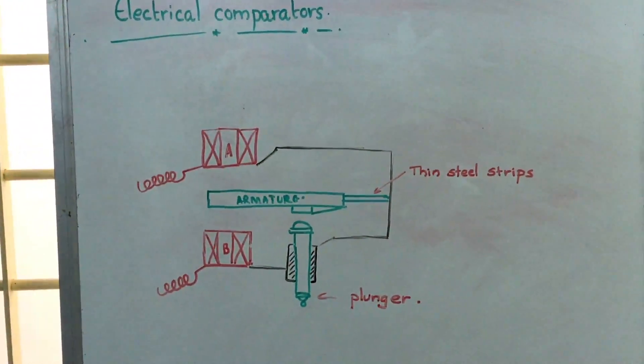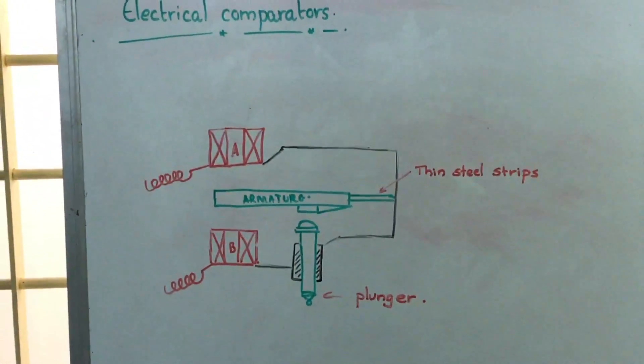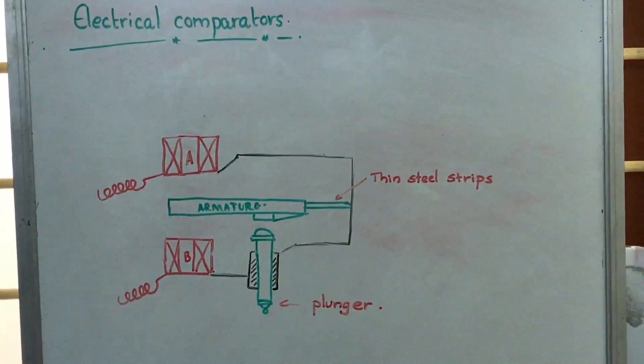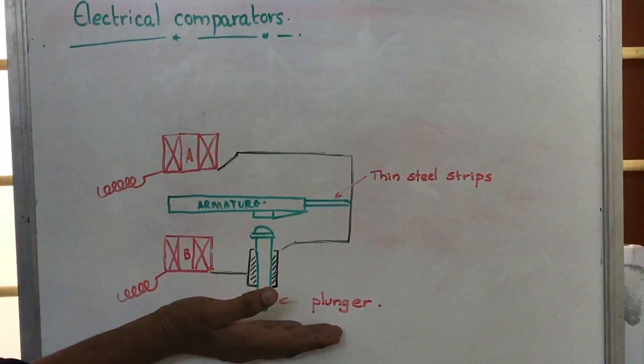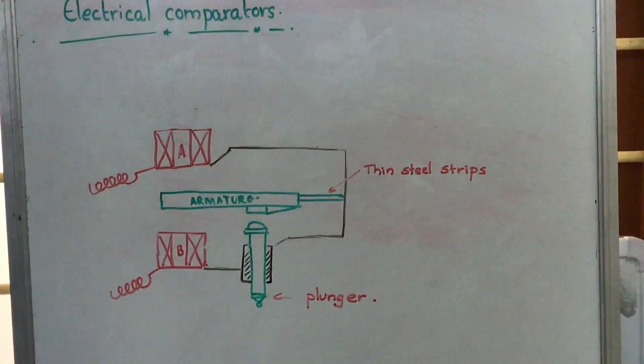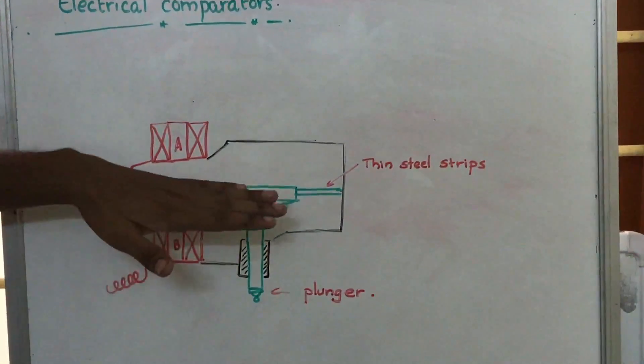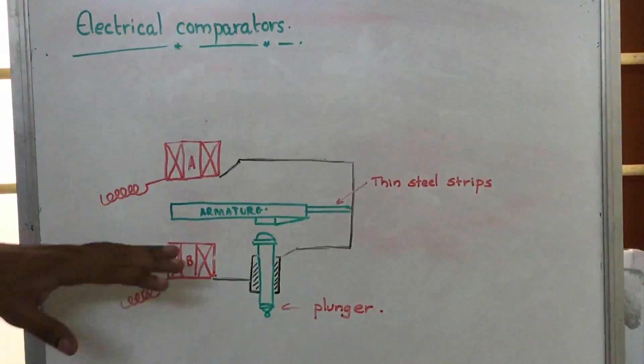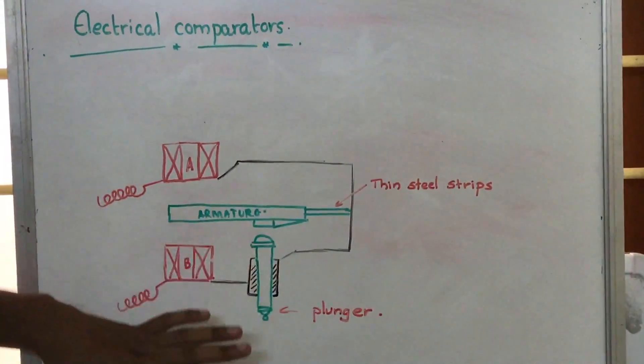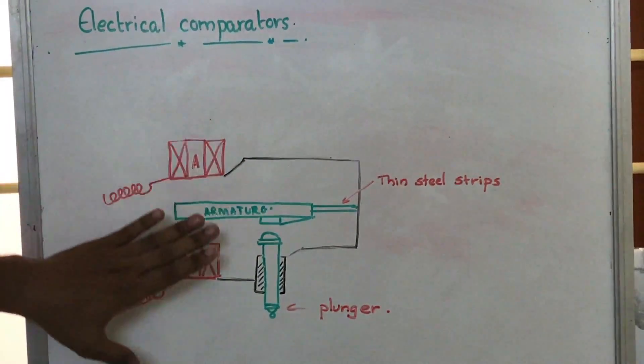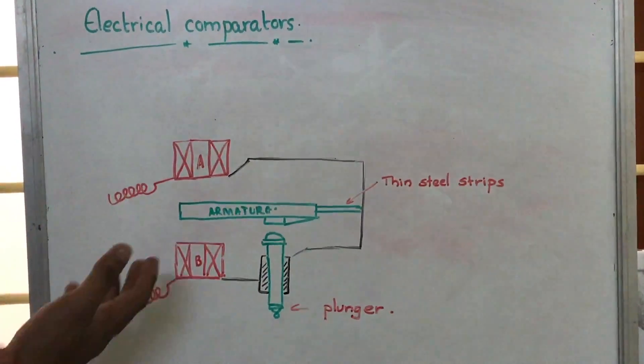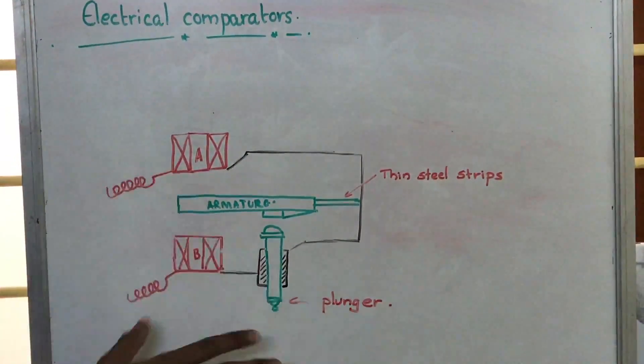When we insert an object whose dimensions will be measured, the plunger will move. Because of the movement of the plunger, this armature will have some deflection. Because of the deflection of this armature, there will be an induced EMF in one of these coils, or some properties like inductive resistance will change.